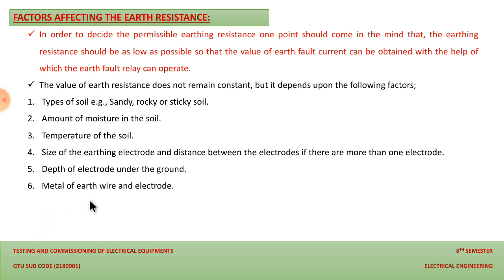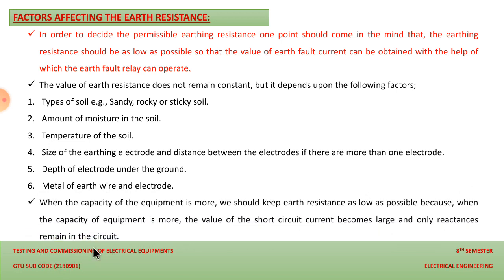And the metal of the earth wire and electrode. Yes, the type of metal that we are using for the earthing is again a major factor. Generally we use GI wire, and the plate we use generally is a copper plate for the earthing. And when the capacity of the equipment is more, we should keep the earth resistance as low as possible. This is the major factor. If the capacity of the equipment is more, we have to reduce the earth resistance as much as possible, and for that we have to pour more impurities and more water at the place where we have placed our electrode.